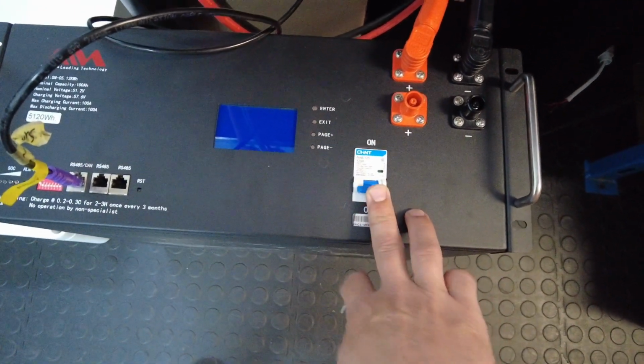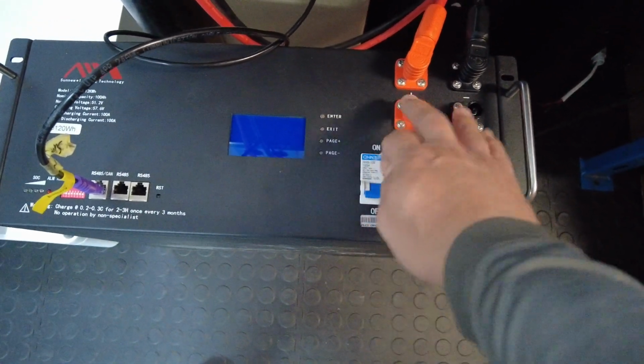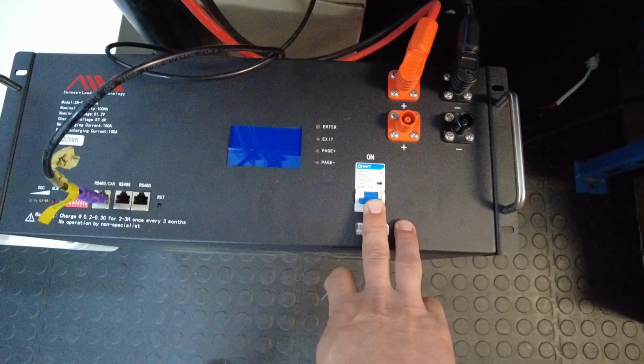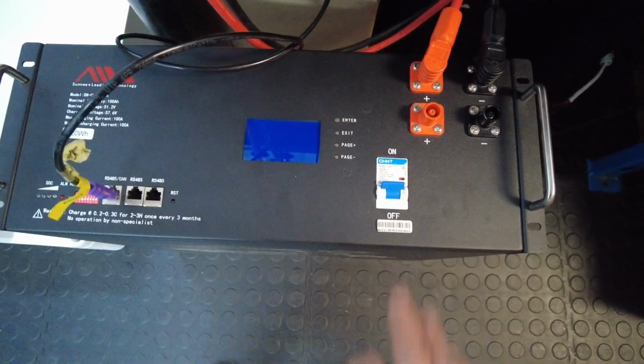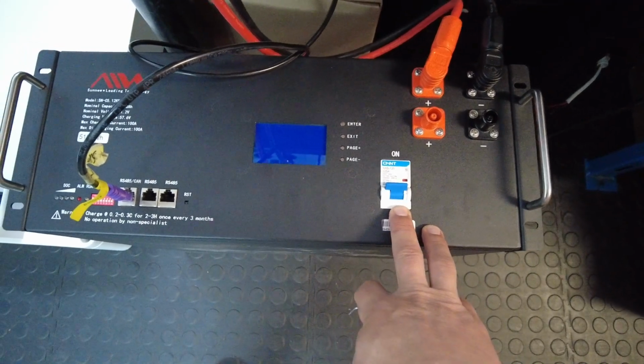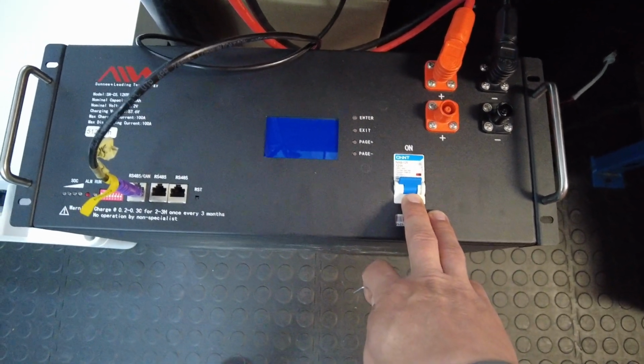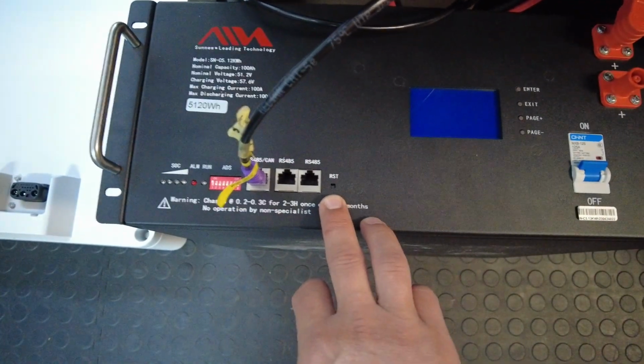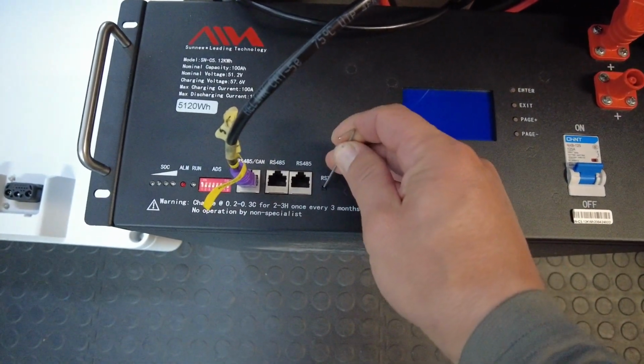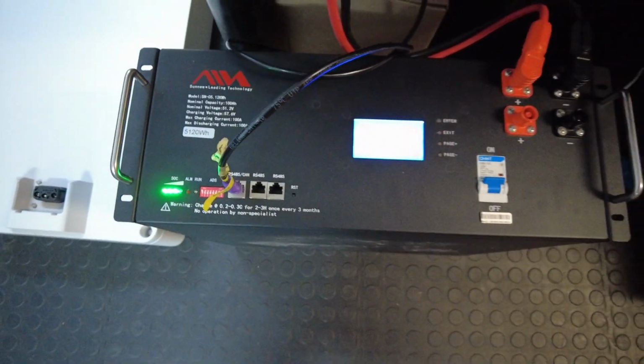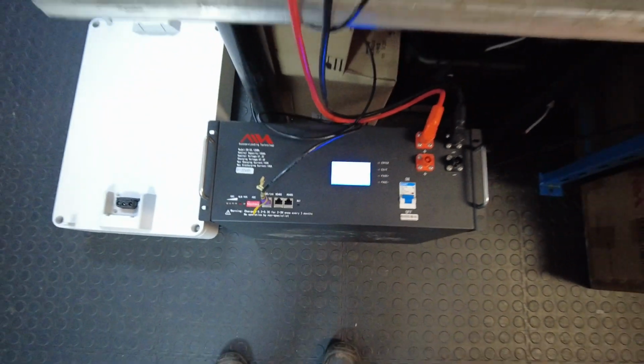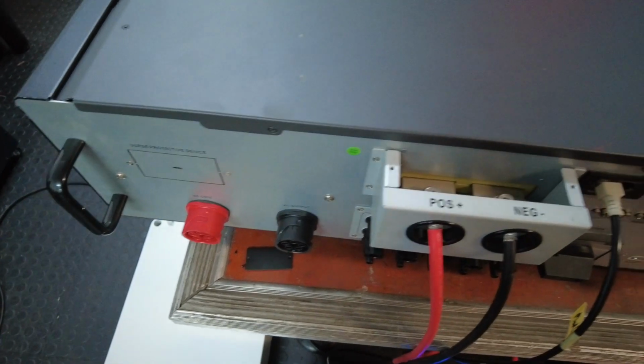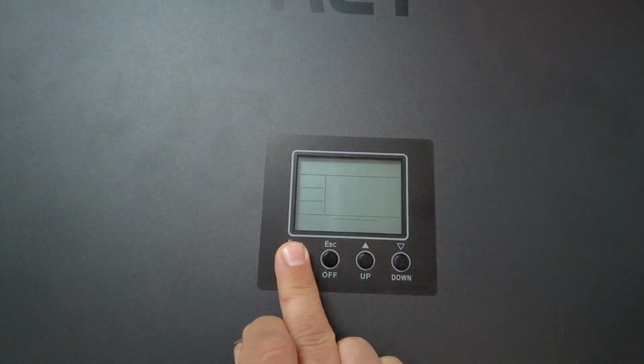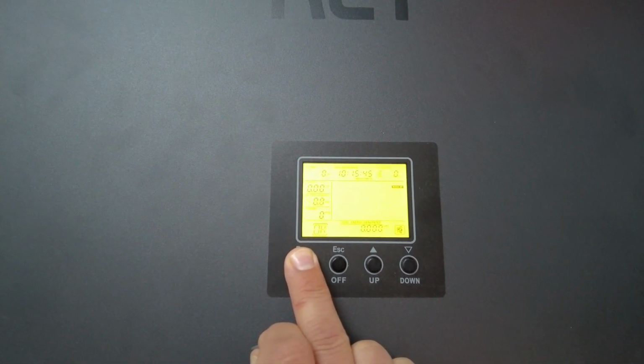Friendly note, this is just an output breaker to shut your contacts down, switch them on and off. It does not actually switch the battery on or off. This is just an isolator. To switch the battery on, you actually need to come to this reset switch. Find something sharp, just to press down onto it, and the battery will start up. I do not have any AC connected to the inverter, so currently the inverter still appears as being off. Long press of the on button will start up the inverter.